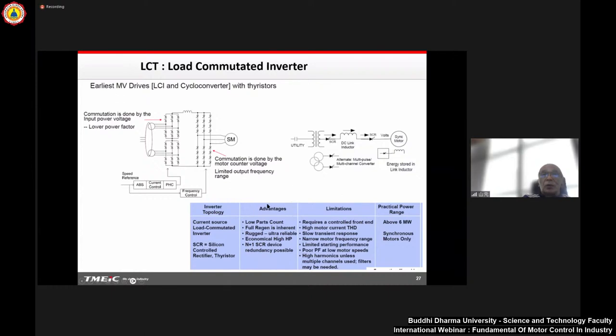The advantage of this configuration is fewer parts compared to voltage source drives, because it's a simple configuration with thyristors - six-phase and three-phase thyristor rectification and a three-phase thyristor inverter section, very easy to make. And regeneration can be done with this configuration - it can control power flow in one direction or also control power flow from the motor side back to the power supply line, so no special circuit is required. However, as I explained, this configuration has very low power factor compared to voltage source drives. Voltage source drive power factor can run at most likely 1.0 unity power factor, regardless of the motor speed.